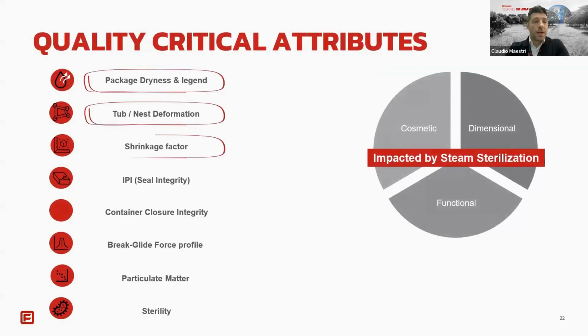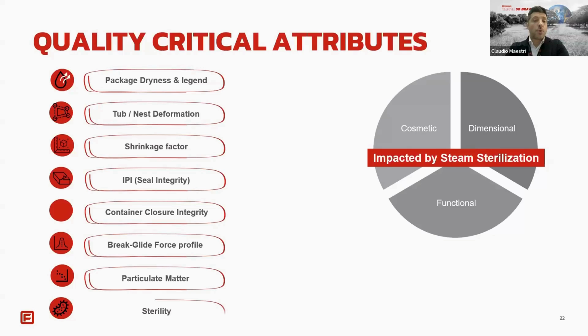The critical quality attributes are physical, chemical, biological, or microbiological properties of the product that must be within a specific range to ensure the desired product quality, safety, and effectiveness. We identify for this specific product the following attributes, and some of these are impacted by steam sterilization, like package dryness, tub and nest deformation, shrinkage factor, seal integrity, and product sterility.